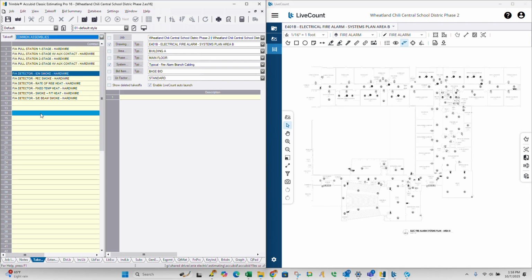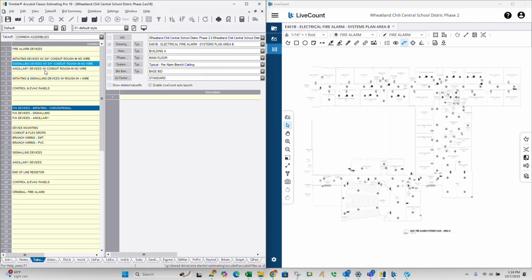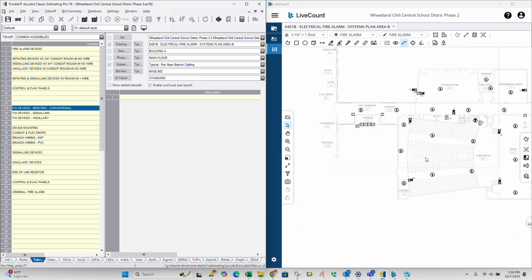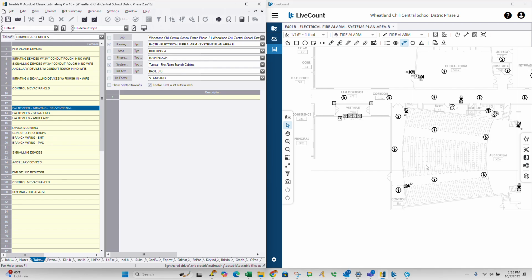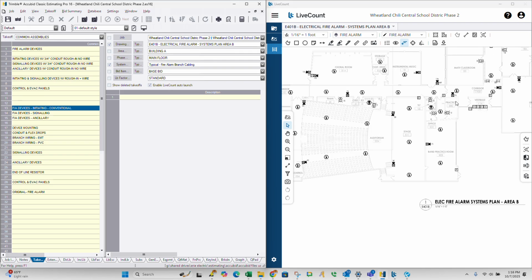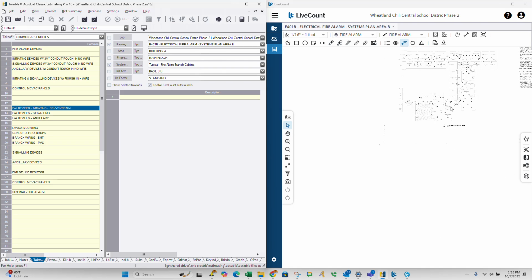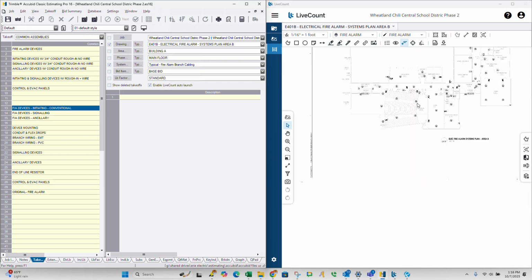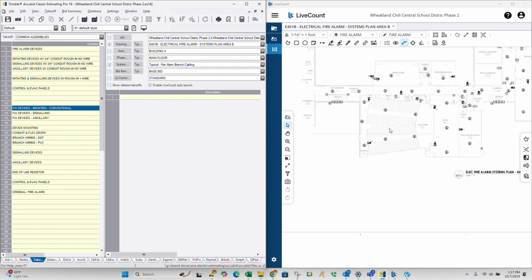So for this, we know the corridor is free air, right? So we could factor doing that free air in there. And let's see here, they should have it on here. But this is where it gets kind of murky, because I usually would just slap some conduit run around the whole place because the free air doesn't really give you the right amount of labor hours for this.